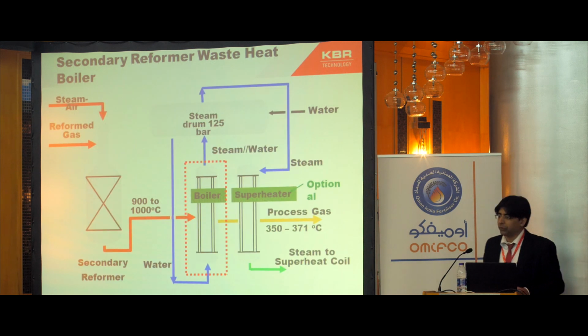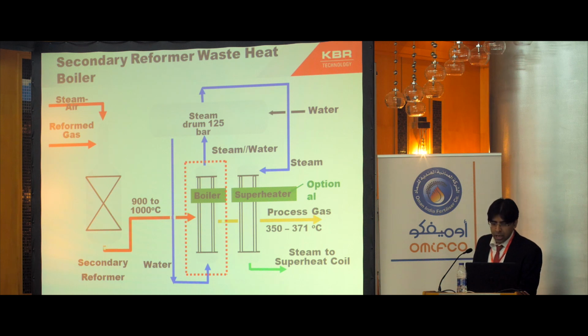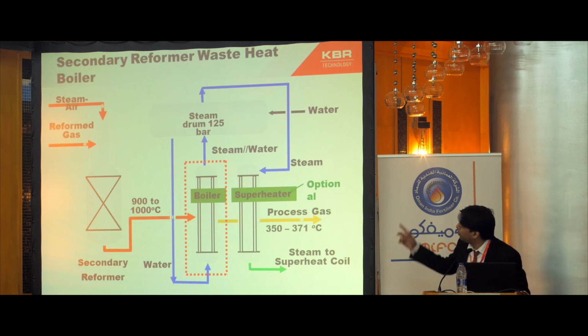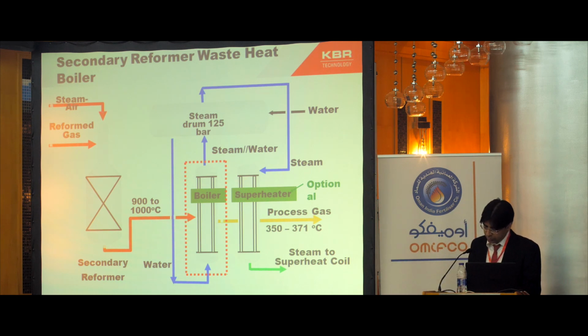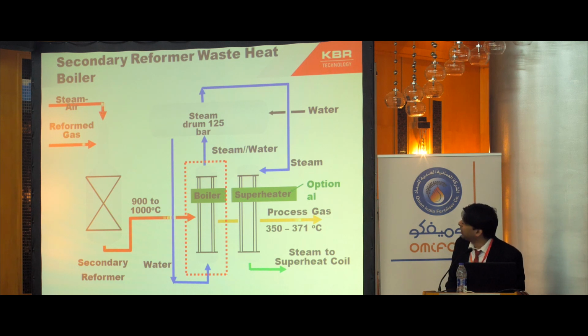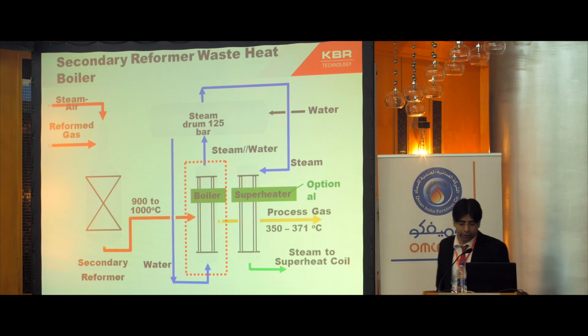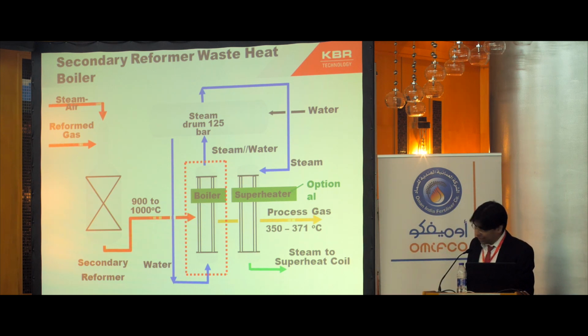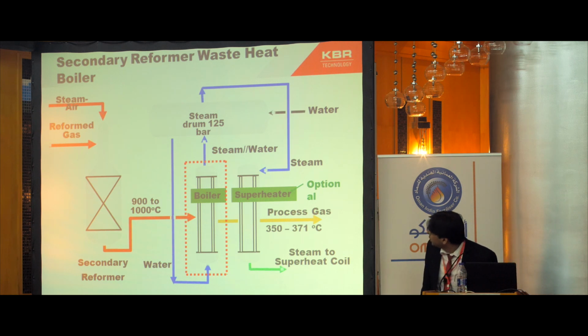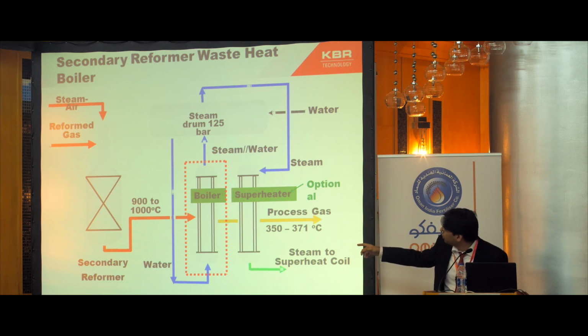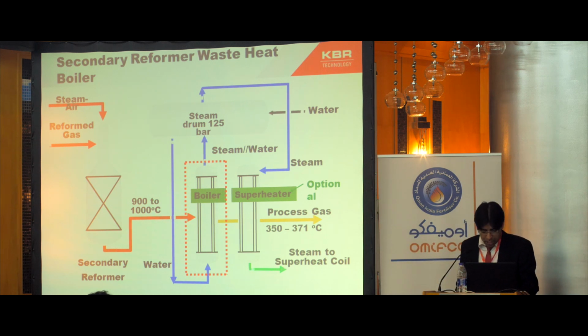This is how the process of the secondary reformer waste heat boiler works. The steam and the reform gas enter from the top, and the combustion reaction takes place. In the catalyst bed, endothermic reactions take place, and the secondary reformer effluent goes out from the bottom to the boiler. The boiler is a natural thermosiphon, which is connected to the steam drum from the top. The boiler feed water can flow from either top or bottom. It goes to the tube side of the boiler and goes to the steam drum. The second exchanger is optional, which can be used either for superheating the steam or producing high pressure steam.